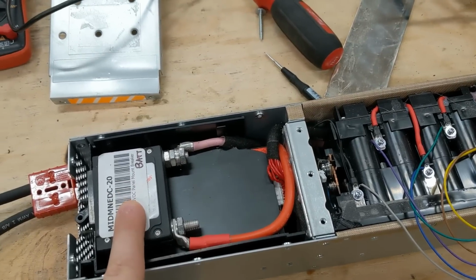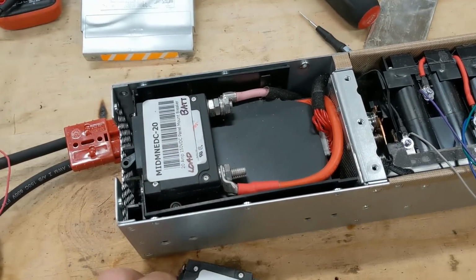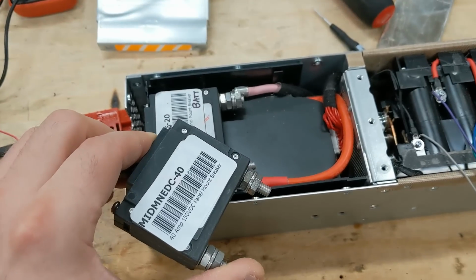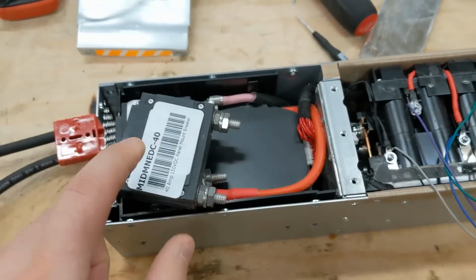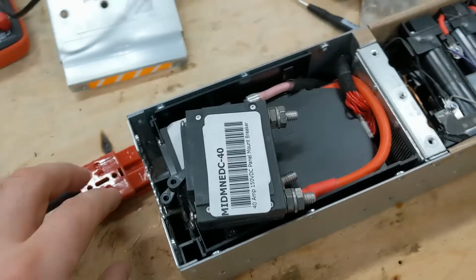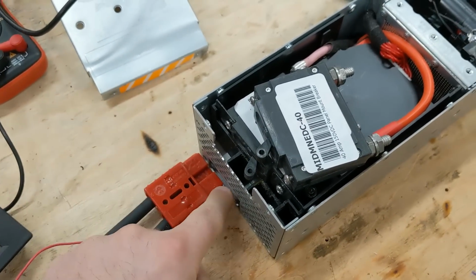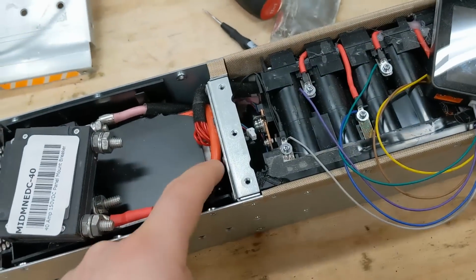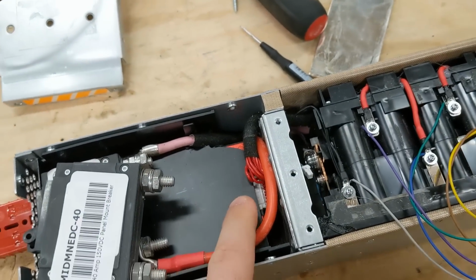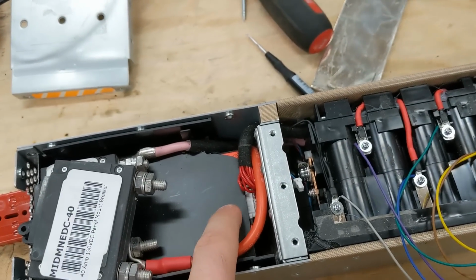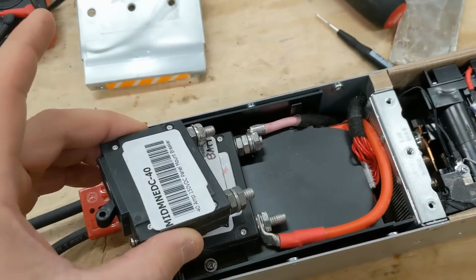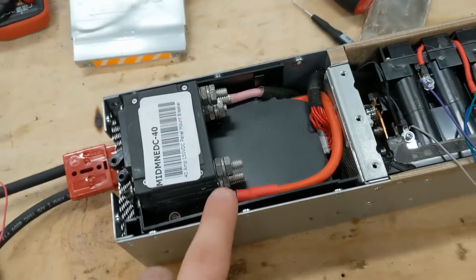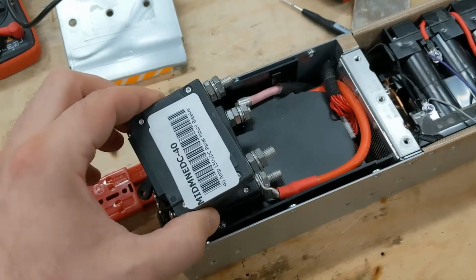But how high can I go with the circuit breaker? I'm going to use this one, a 40 amp. The reason I chose the 40 is because these Anderson plugs are 50 amp plugs, and the BMS can do 50 amps charge and 60 amps discharge. So I like the circuit breaker to be a little bit smaller than the other things - the circuit breaker is always the weakest link.